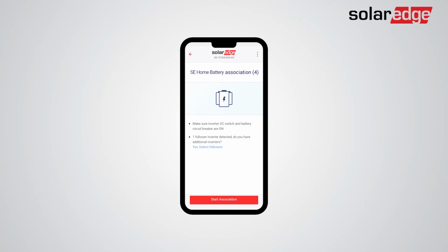The next step is tapping Start Association. Now, the batteries will automatically be associated with their connected inverters. This entire process should take up to 2 minutes. Battery association is a process of connection verification of the battery to the inverter and is performed in its entirety with safe, low DC voltage.